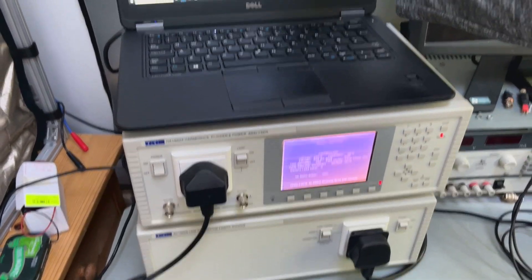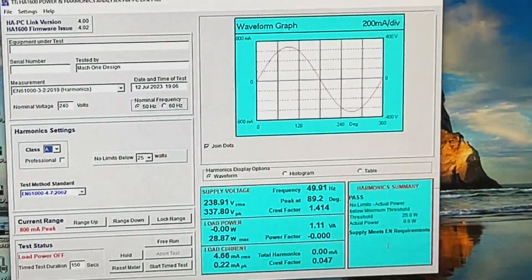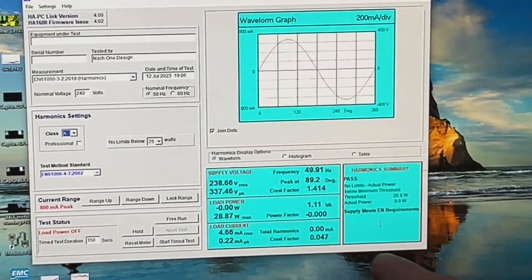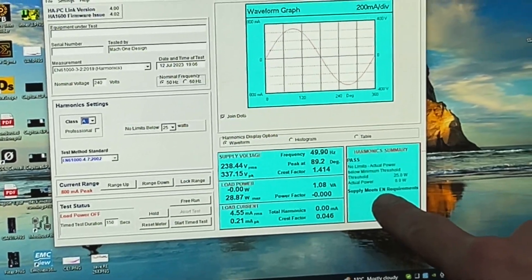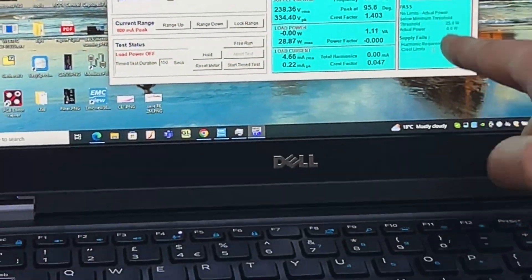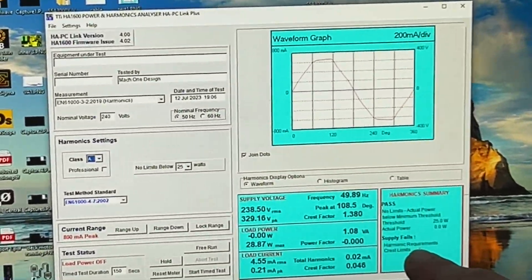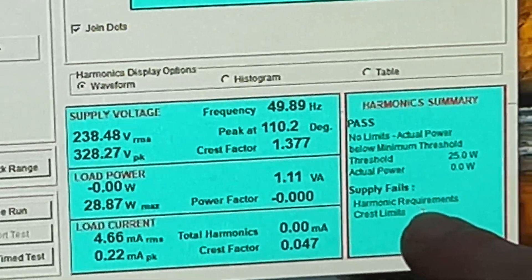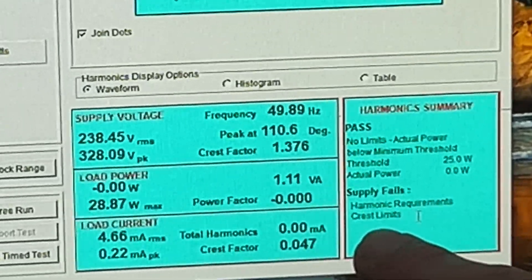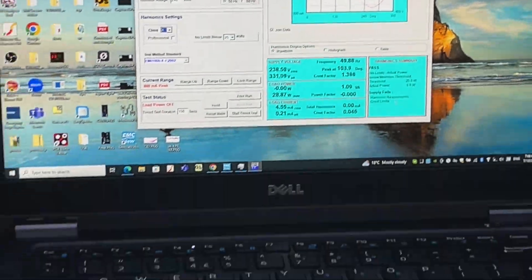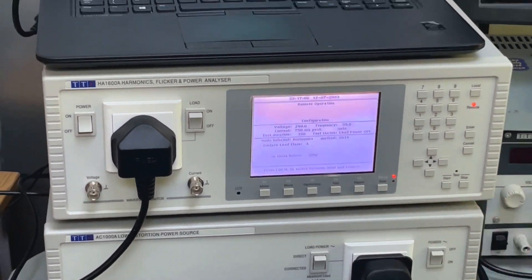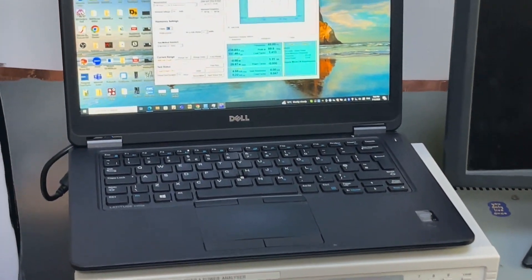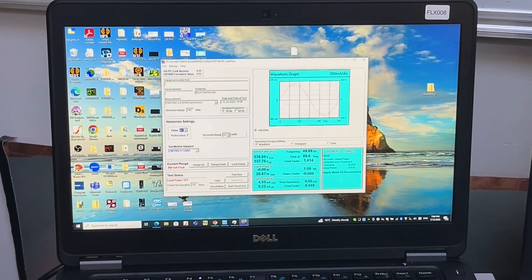You can see here the mains voltage is close to a purely sinusoidal waveform and also it gives you the message saying supply meets EN requirements. Whereas in the previous case you can see supply fails to meet the EN defined requirements because the crest limit is wrong, harmonics is wrong. So the clean AC source gives us a good starting point in this case.